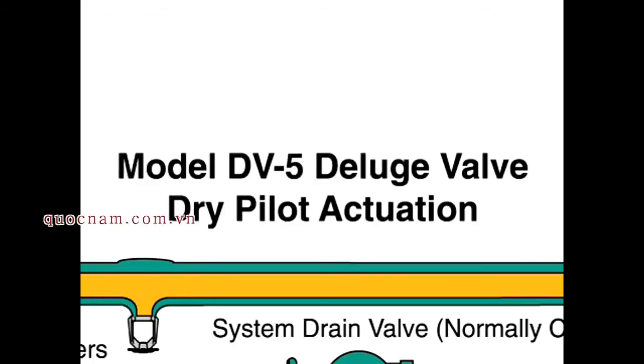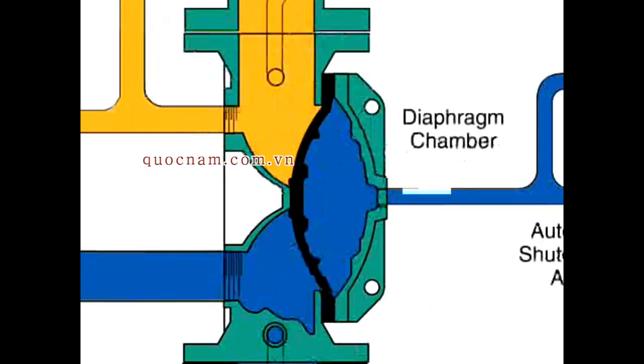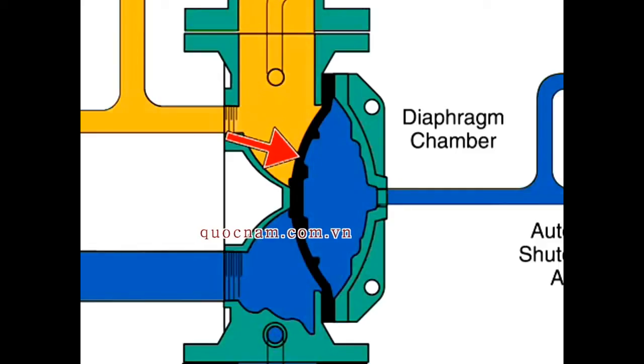The DV5 deluge valve with dry pilot actuation. The model DV5 deluge valve is a diaphragm-style valve that depends upon water pressure in the diaphragm chamber to hold the diaphragm closed against the water supply pressure.